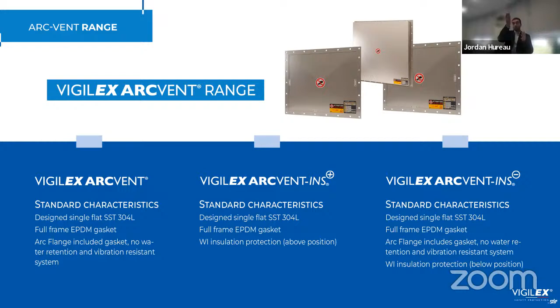is a stainless steel membrane cut on three sides with breaking points. And those breaking points are calibrated to resist a determined pressure called P-stat, the static opening pressure. So when you have an explosion and the pressure reaches the P-stat, the breaking points will break, like the name, and will open the panel to release the pressure of the explosion outside. Here, I will show you a little movie from one of our tests in Ineris.